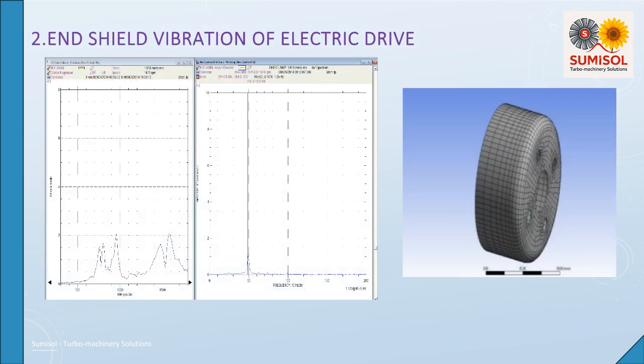The second case is related to a high-voltage electric drive. During installation of a heavy-duty electric motor, cracks were found at 2 different places of the end shield. To meet the installation and commissioning schedule, the shields were replaced by locally fabricated shields but with slightly reduced thickness. During commissioning, the velocity transducer installed on the non-drive/exciter end of the generator measured high 2xn vibration in the axial direction at a frequency close to the equipment operating frequency.